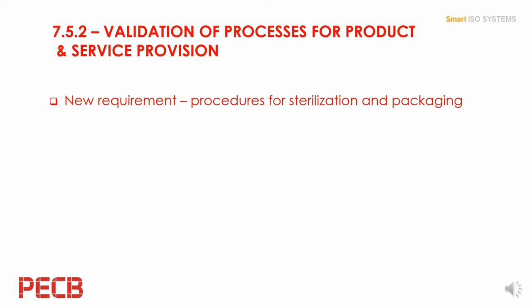There's now an added requirement to include procedures for validation of sterilization and packaging. If you comply with the European Medical Device Directive, you will be already doing this. Now the new proposed standard is going to call for it. There's also an added reference to ISO 11607 standard for packaging terminally sterilized medical devices. This is just another reference you can use as guidance to help you comply with the 13485 requirements.